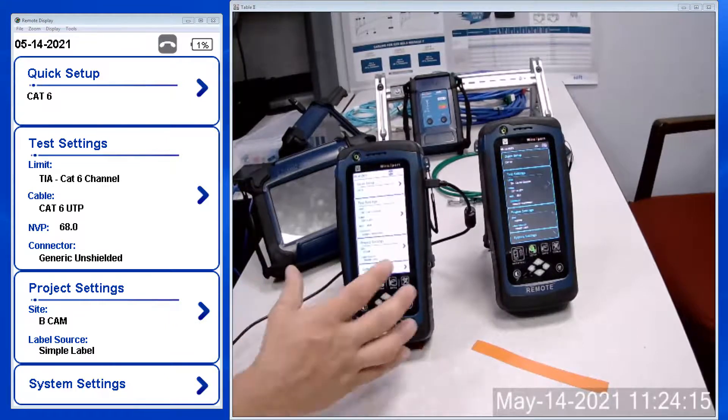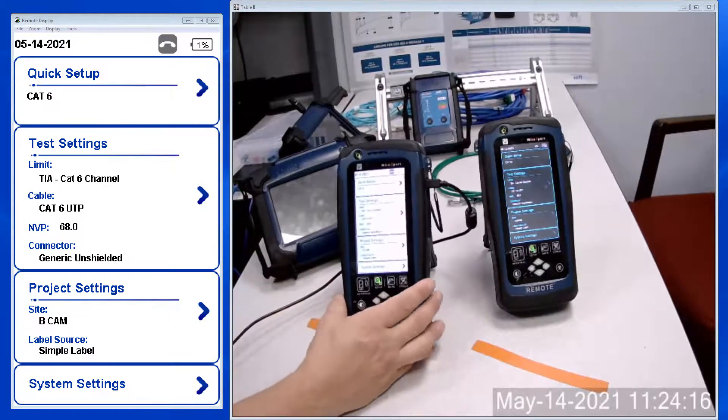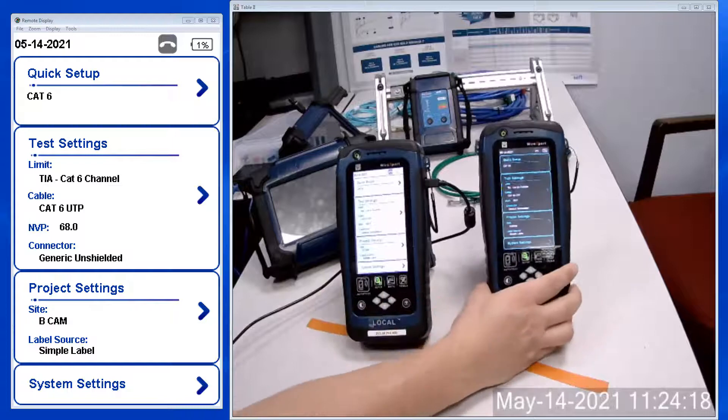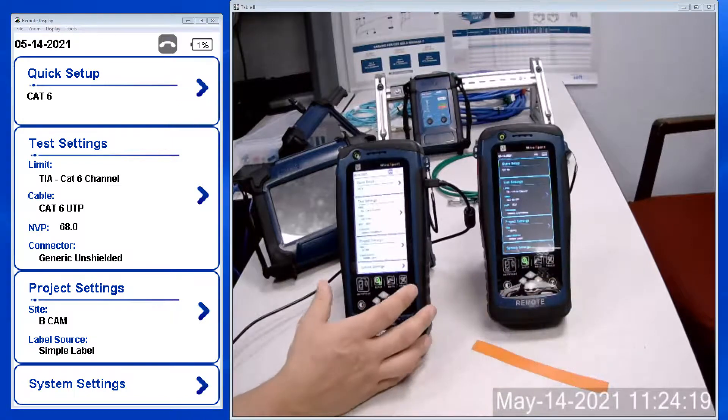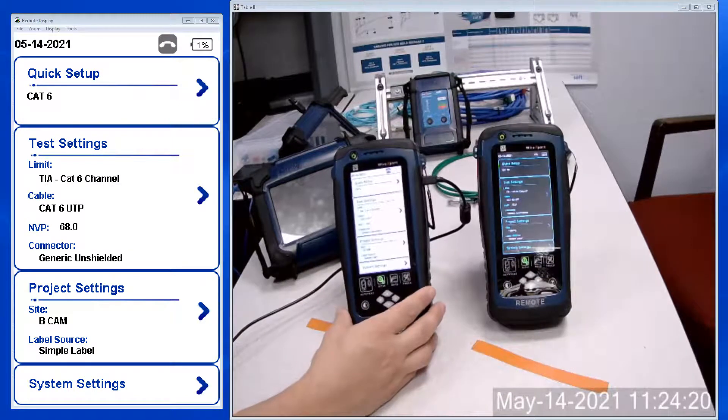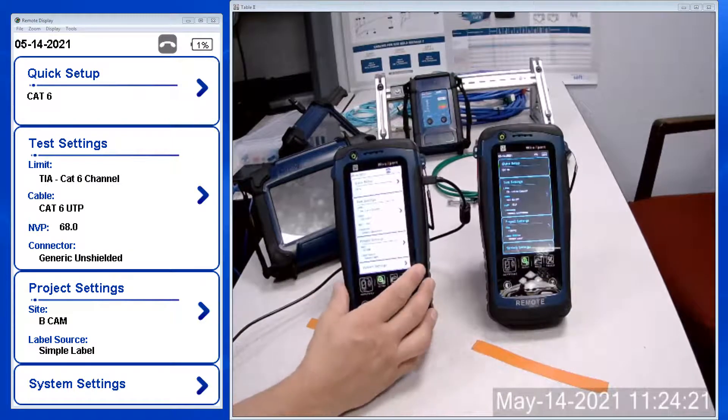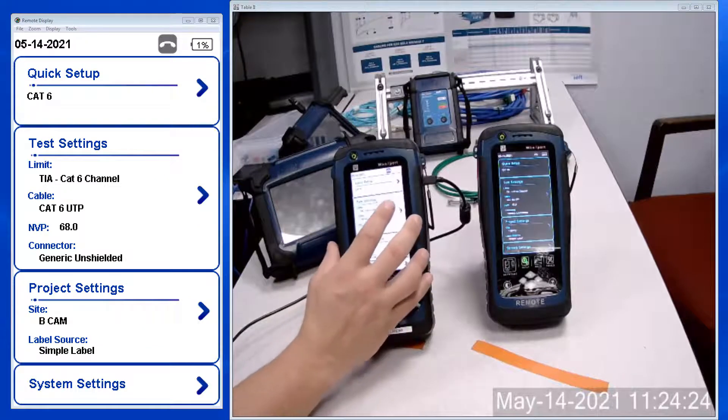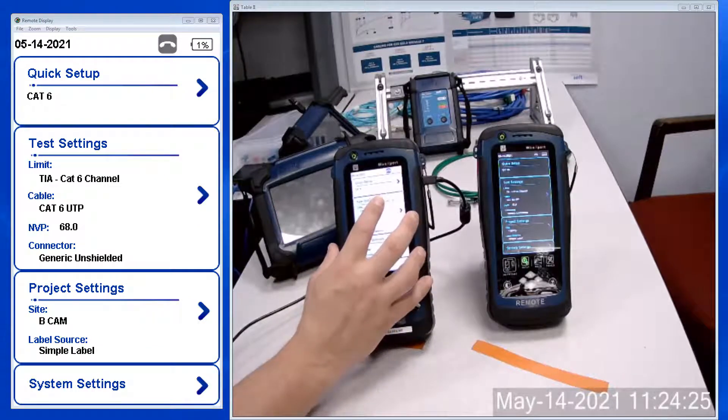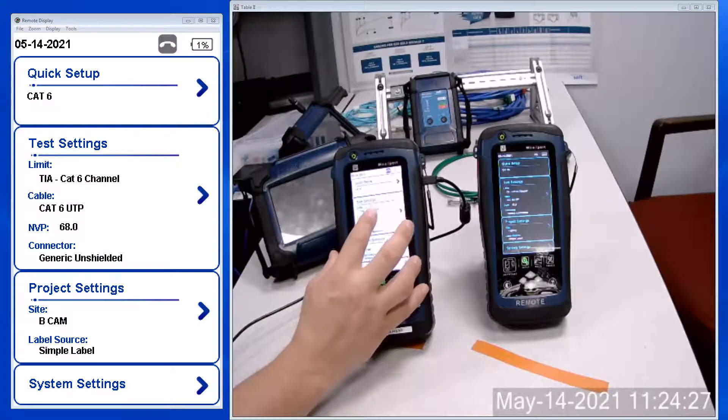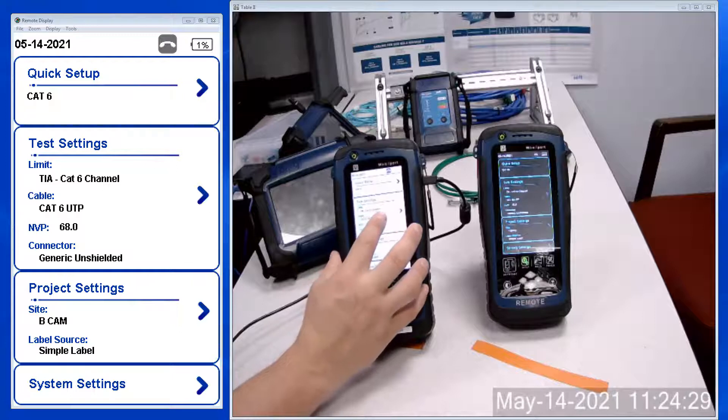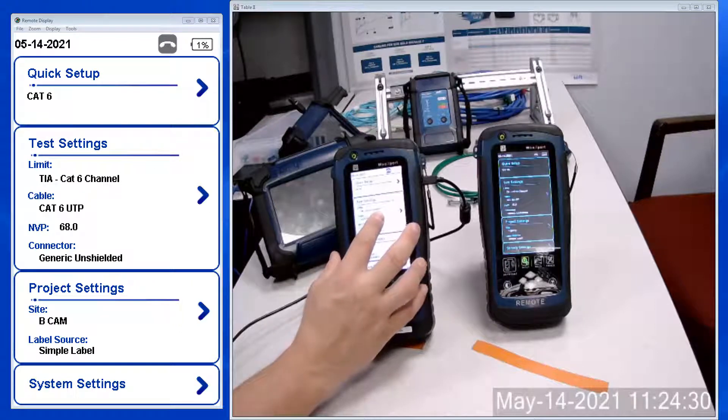So this is the Wire Expert 4500 local unit, this is the remote unit. You would choose those settings on the local interface here. This is the main setup screen. You can see here we have test settings where there's currently a Cat 6 channel selection with Cat 6 UTP cabling.